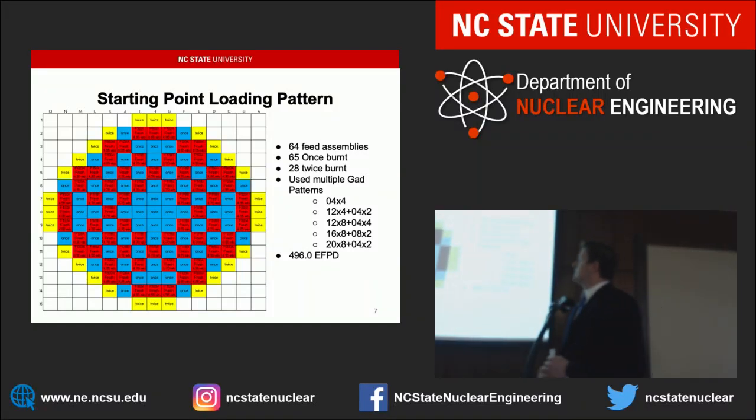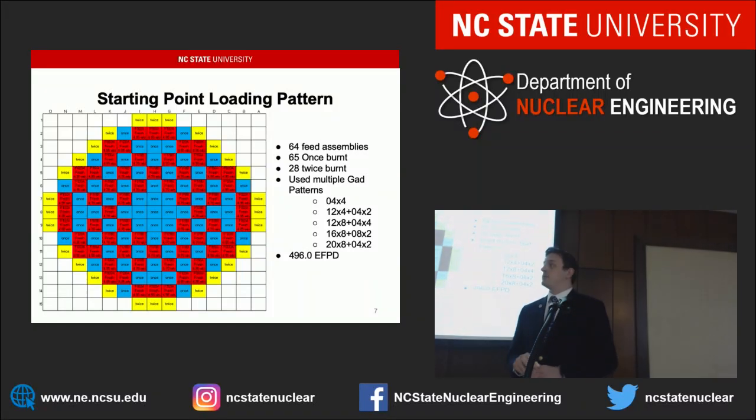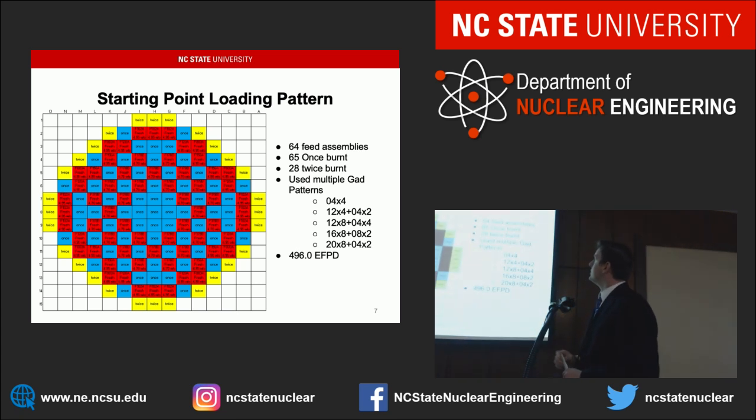This was the loading pattern that Framatome provided to us. As you can see in this loading pattern, there are 64 fresh fuel assemblies, 65 once burned and 28 twice burnt. So there's a significant amount of burnt fuel in the core, along with multiple GAD patterns, as we already mentioned, going up to 8%. And this ran for 496 effective full power days. So we were looking to extend that design.